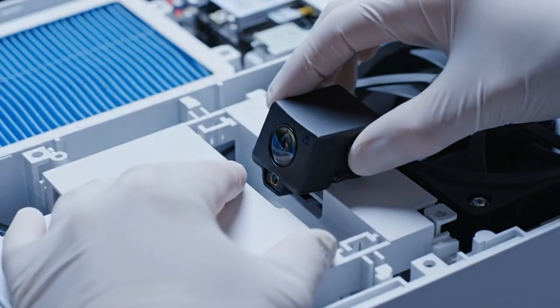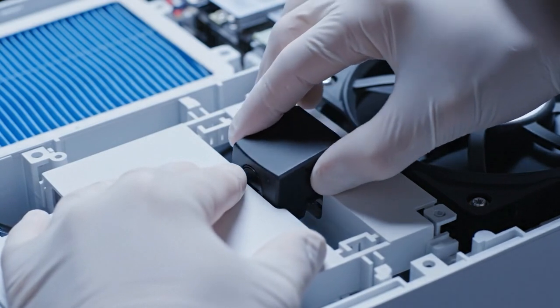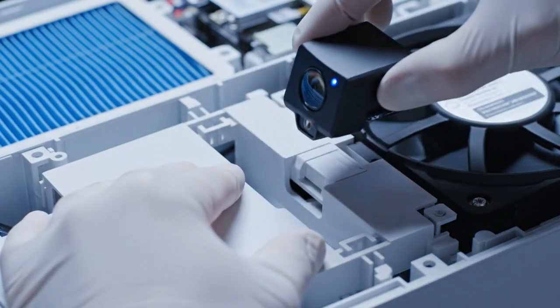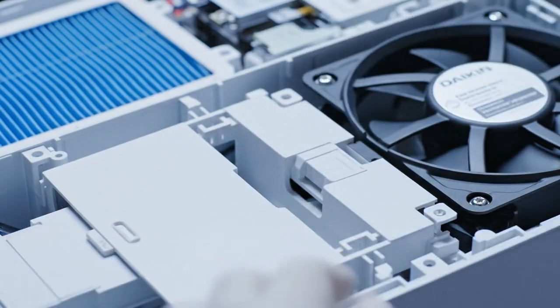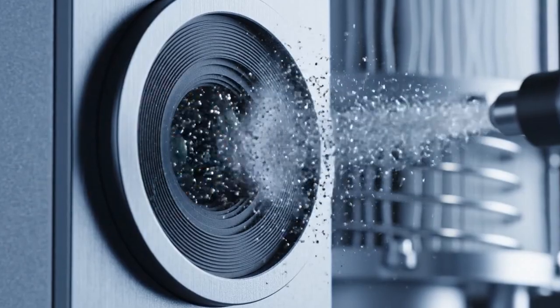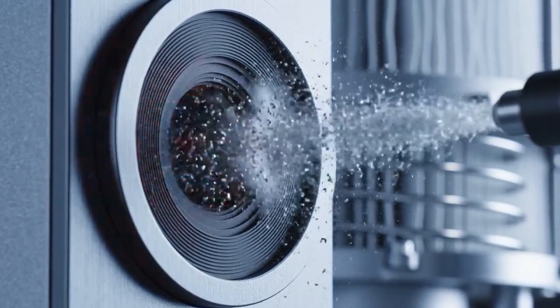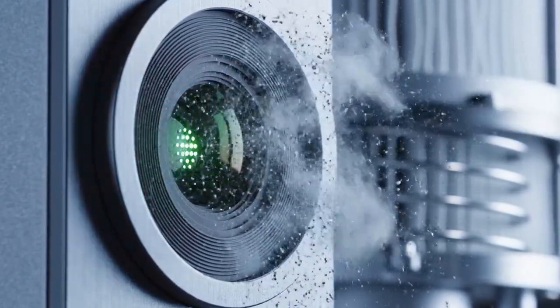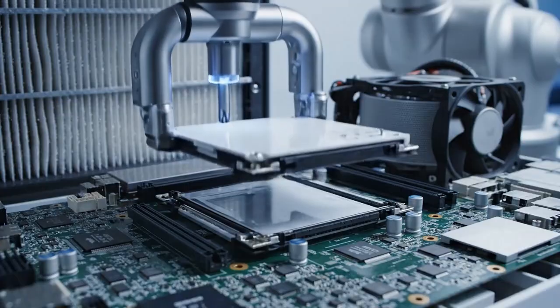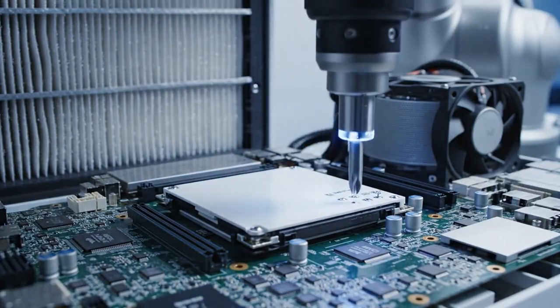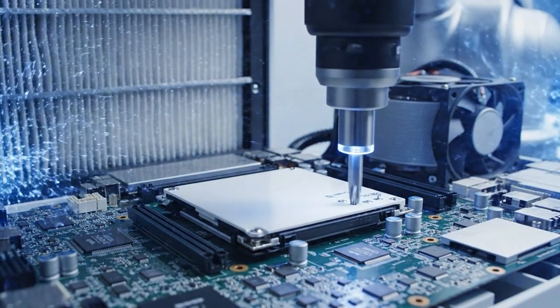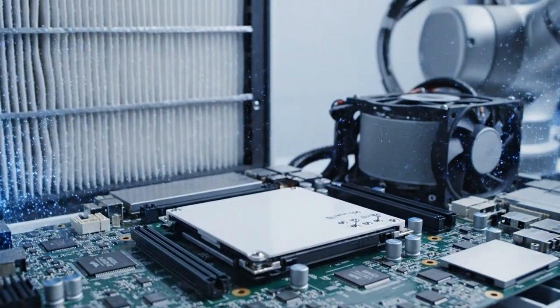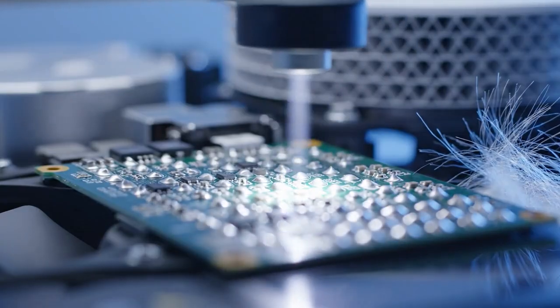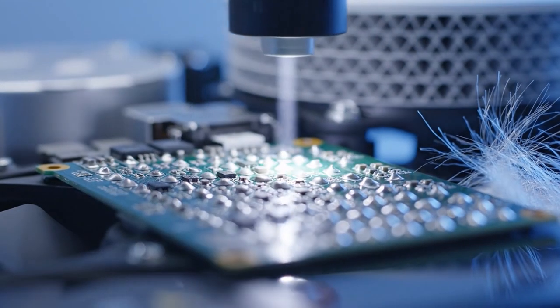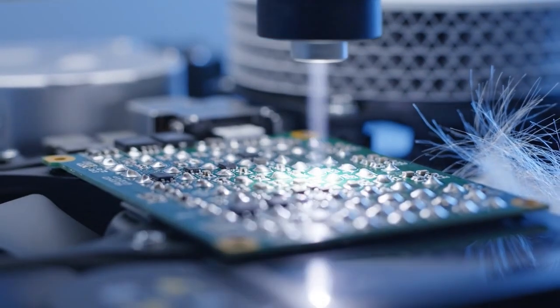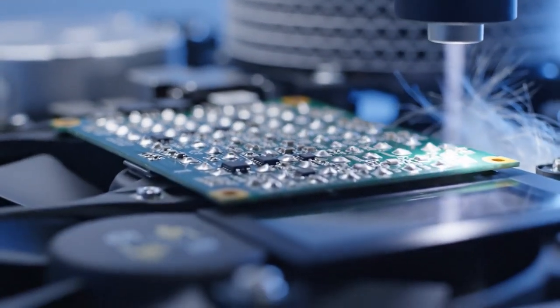Sensing the invisible. Installing the optical dust sensor that provides real-time feedback on air quality to the control system. Calibration for accuracy. Ensuring the sensor can reliably detect the smallest changes in airborne particle concentration. Environmental intelligence. Integrating the module that allows the machine to auto-adjust operation based on room conditions. Display reliability. Ensuring every connection on the control interface is permanent and robust.